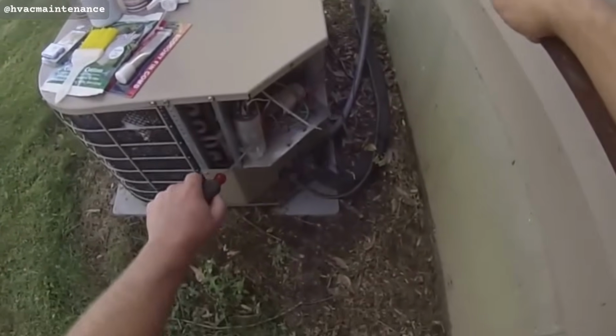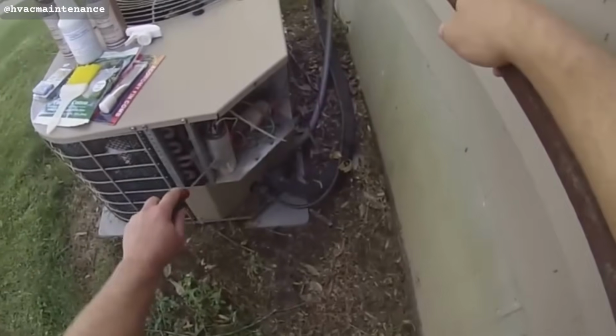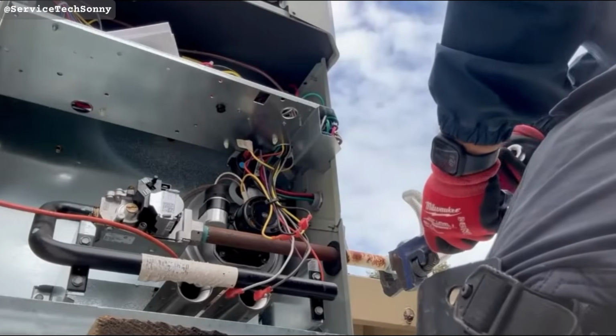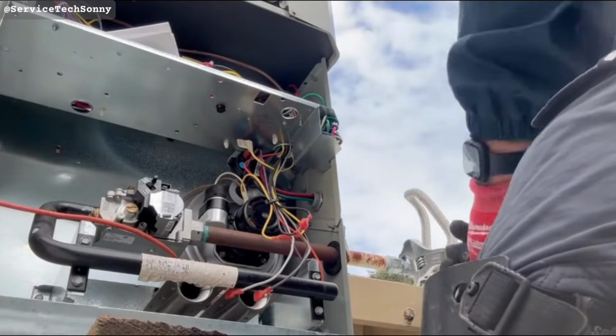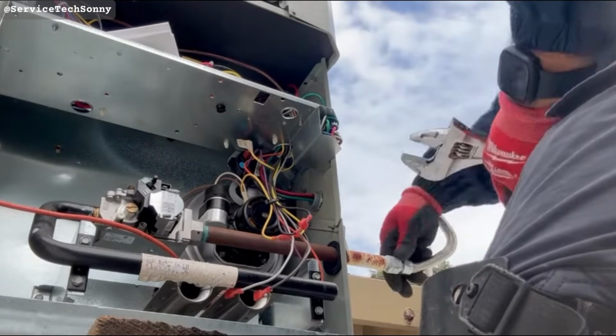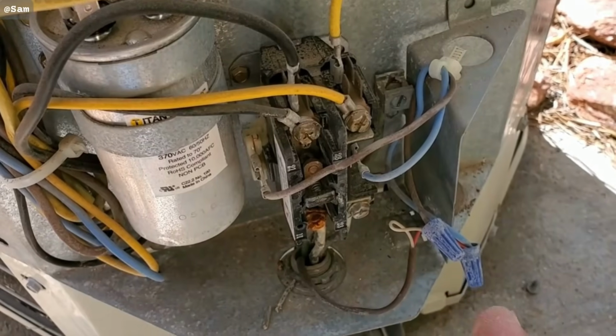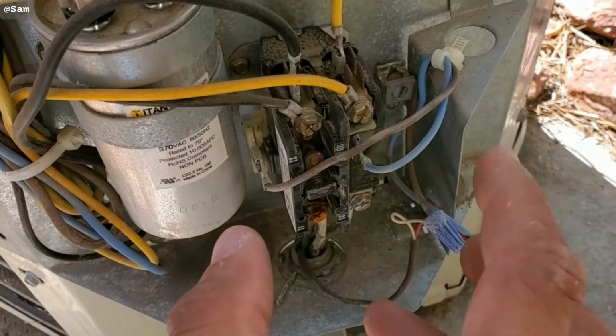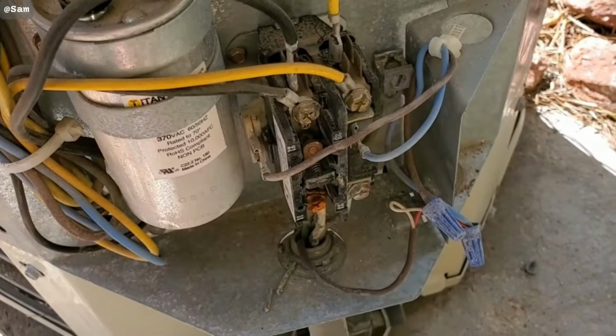Before anyone says it in the comments, yes, I know the common belief is that a bigger AC cools the house faster, and that's a good thing. It cools the air faster, but it doesn't pull humidity out because the runtime is too short for moisture removal. You end up with a cool, clammy house and a dying compressor.